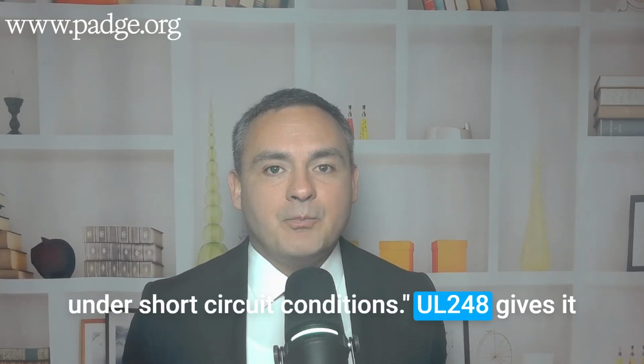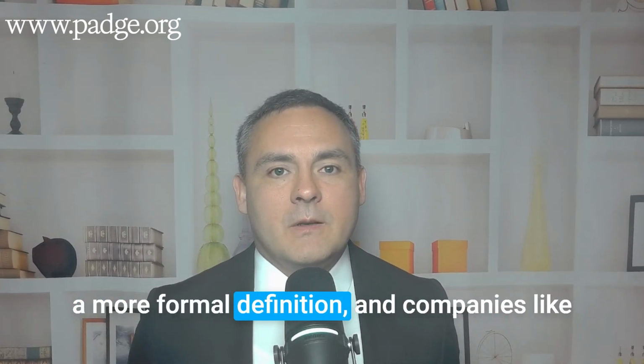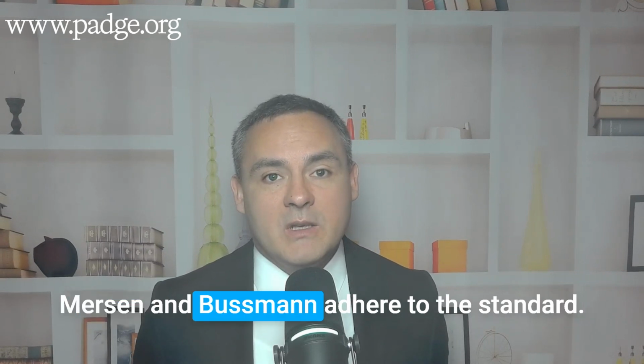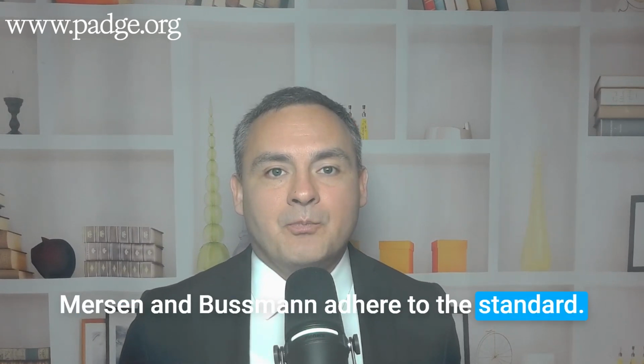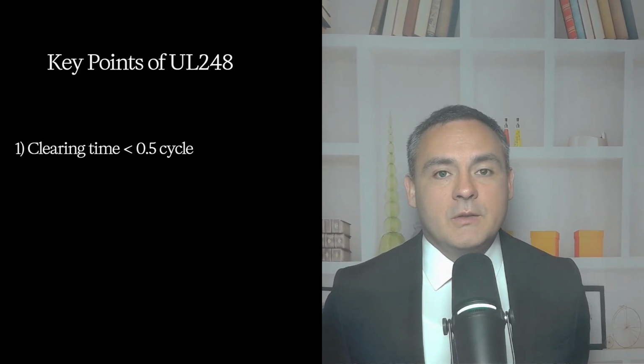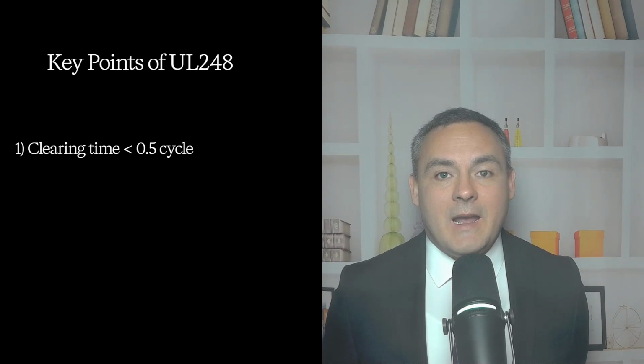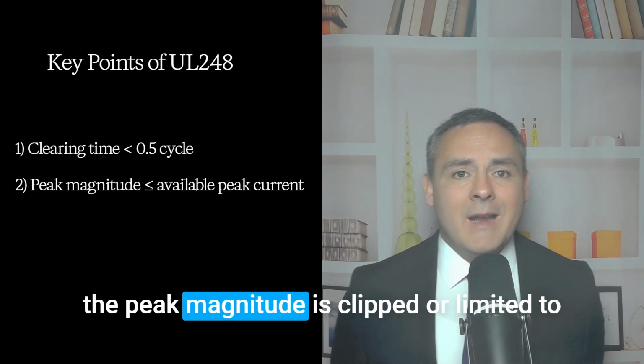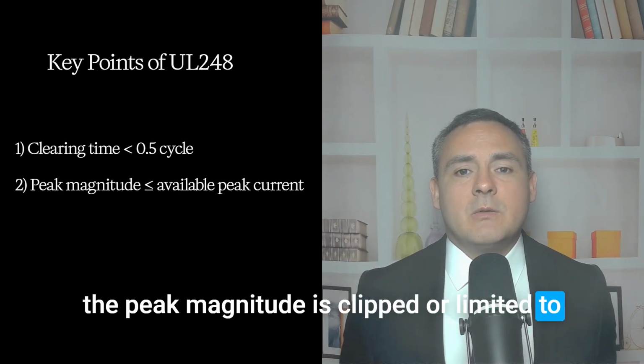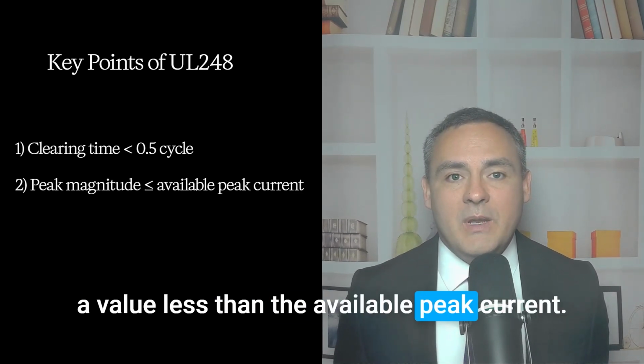UL 248 gives it a more formal definition, and companies like Mersen and Bussmann adhere to the standard. The two things to look for per UL 248 are clearing time in less than half a cycle, and the peak magnitude is clipped or limited to a value less than the available peak current.